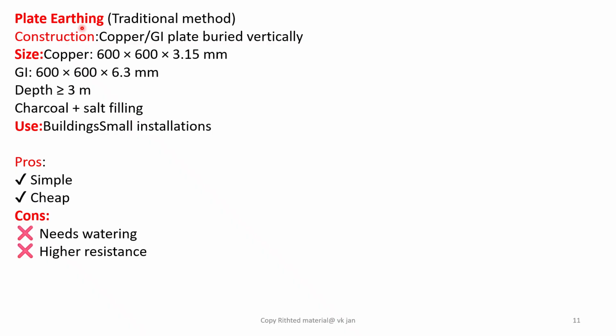Plate earthing is a traditional method and it implies copper or GI plate which is buried vertically. Size may be 600 by 600 into 3.15 mm thickness. In case of GI, it is 600 by 600, but thickness is just double of the copper. Depth is equal to or greater than 3 meter.